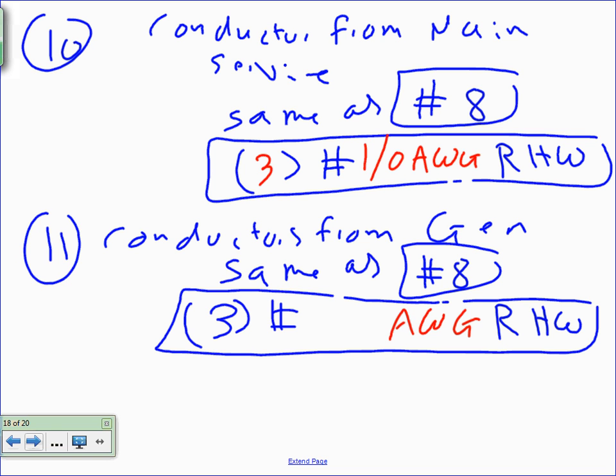And the second one, guys, is the conductor from the generator, same as number 8. So that would be 3 conductors of how many? 1 aught. 3 conductors 1 aught. Any question, guys, about 10 and 11? Straightforward.